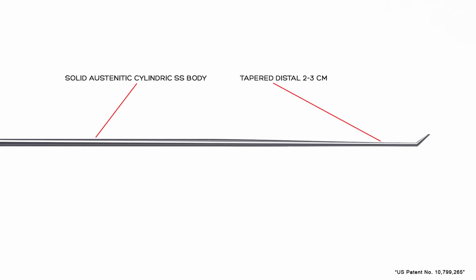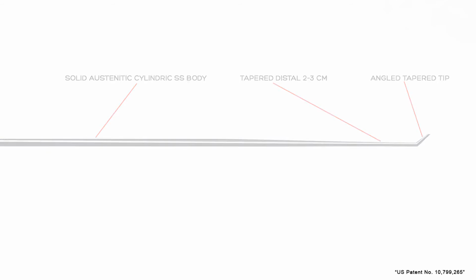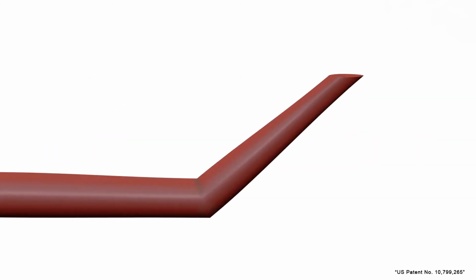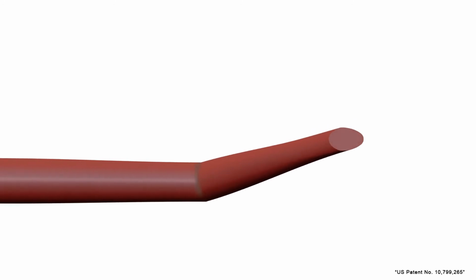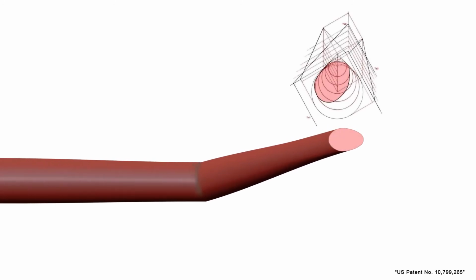A stylet can be defined as a solid austenitic cylindric stainless steel body, uniformly tapered around the distal 2 to 3 cm, ending with an angled tapered tip. In addition, the piercing properties of the stylet are greatly enhanced by its elliptic egg-shaped tip surface. Therefore, this instrument holds greater piercing and crossing capabilities than any other device ever used inside the vascular bed.